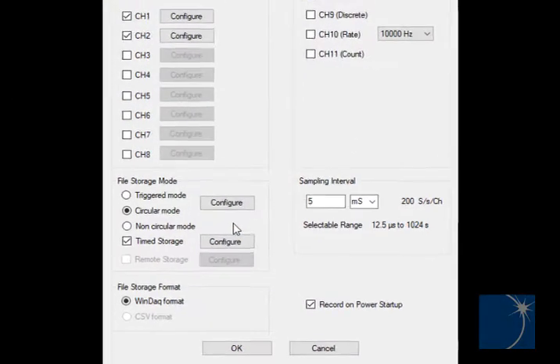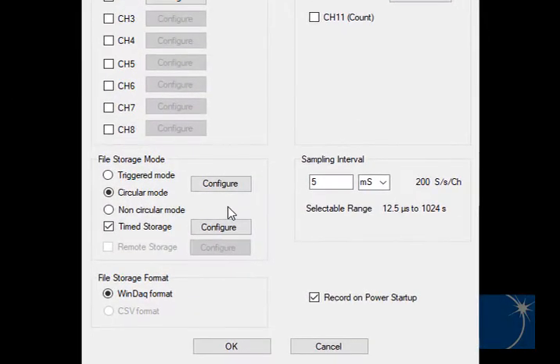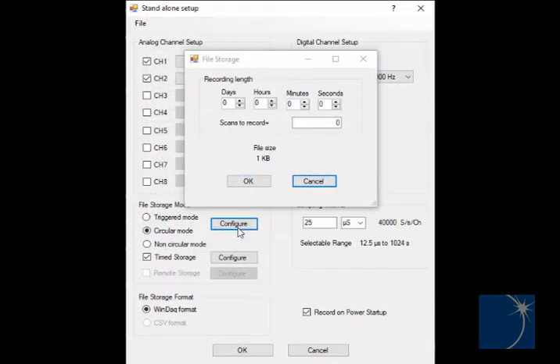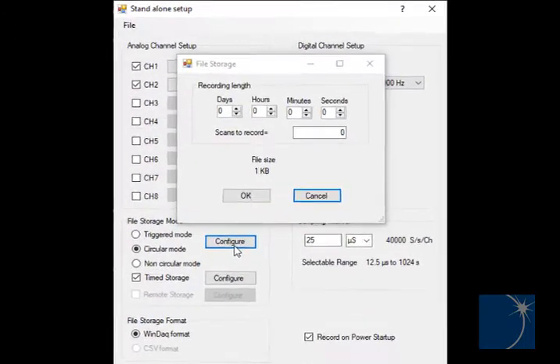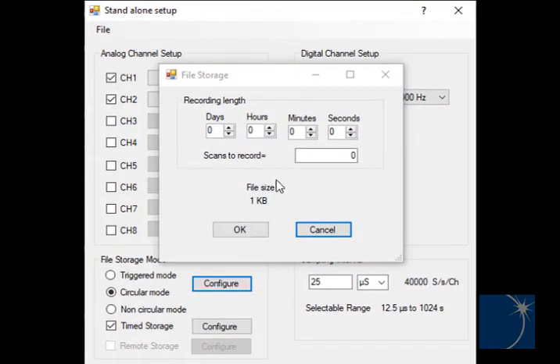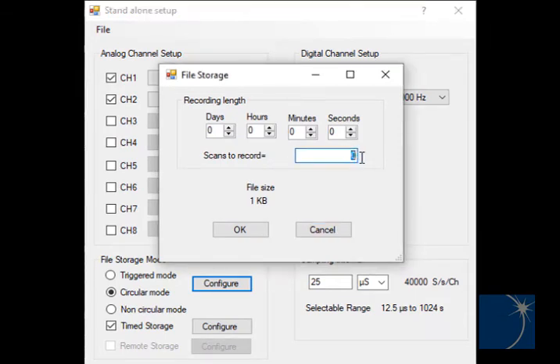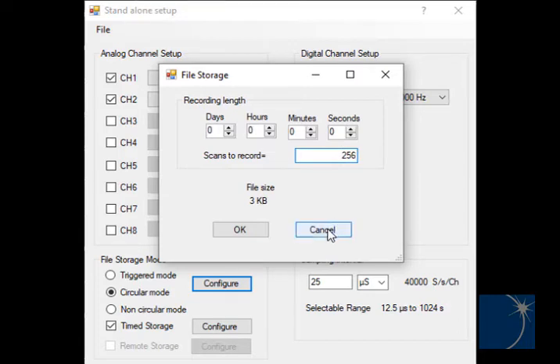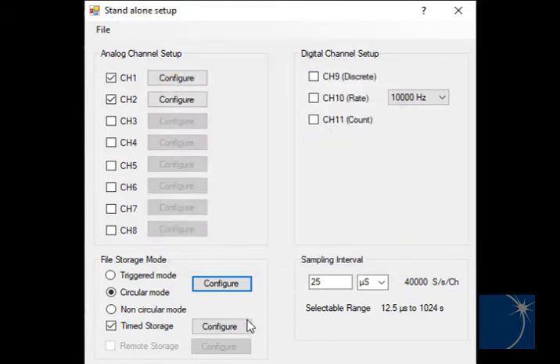With circular mode selected, click the configure button to choose a recording length. You can enter a number of days, hours, minutes, or seconds, or a number of scans. A scan equates to one data point from each enabled channel. Timed storage is also available in circular mode.